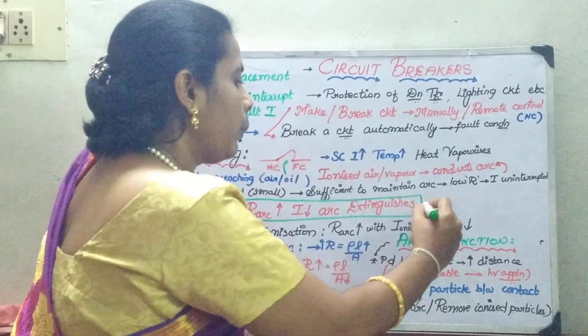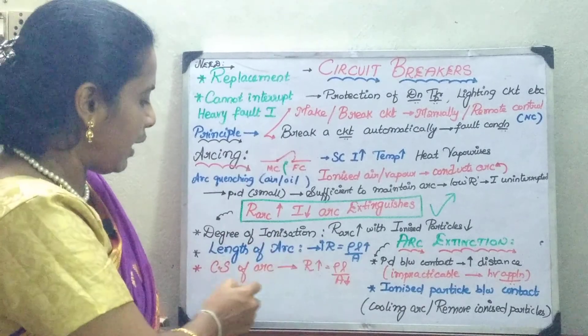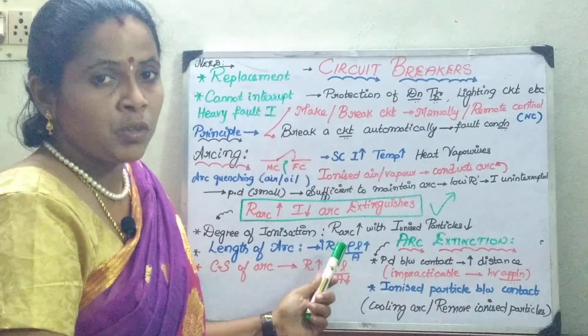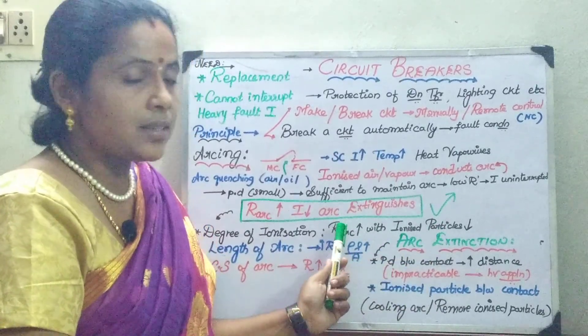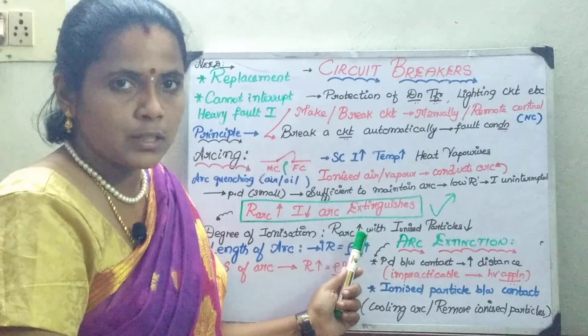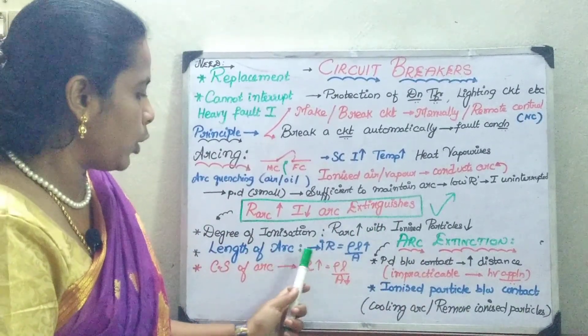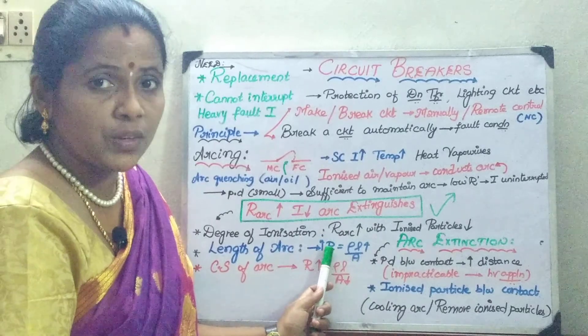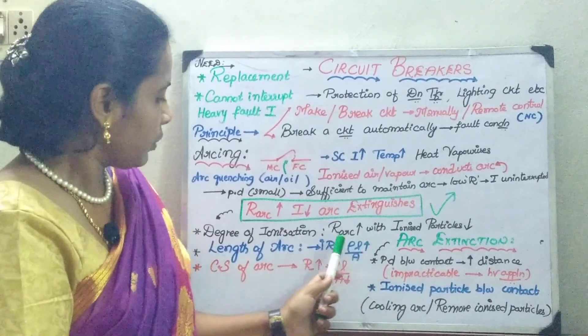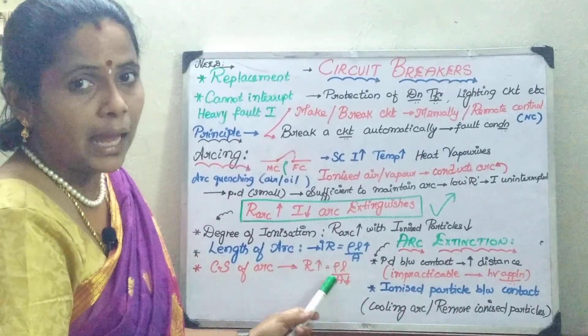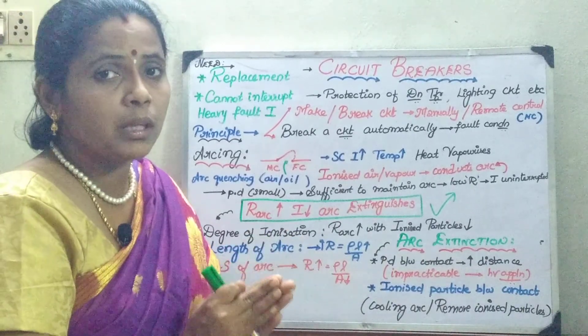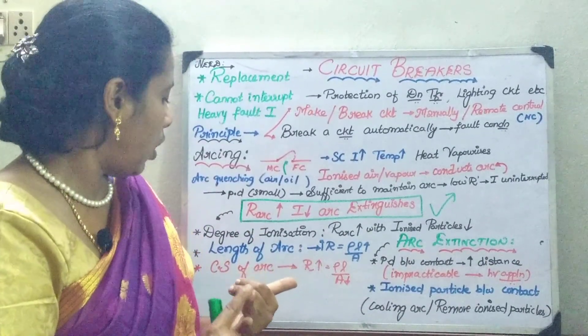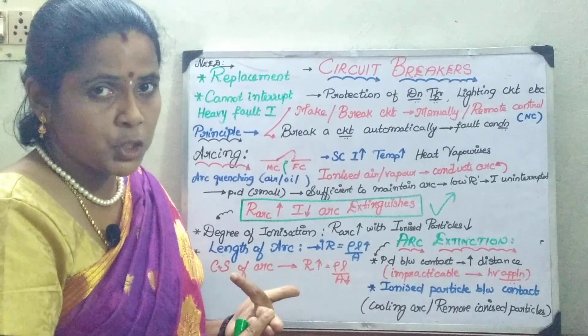Now we will see the factors that contribute to increasing the arc resistance. The first is the degree of ionization — whenever the ionized particles decrease, we can increase the resistance of the arc and thereby quench the arc as soon as possible. The second factor is the length of the arc. Using the general formula R = ρL/A, if we want to increase the arc resistance, that is facilitated by increasing the length of the arc. The third factor is by reducing the cross-section of the arc, we can increase the arc resistance.